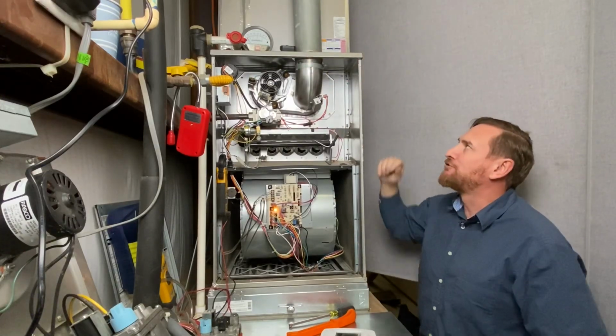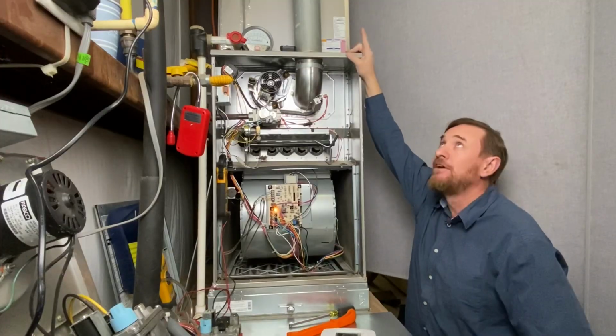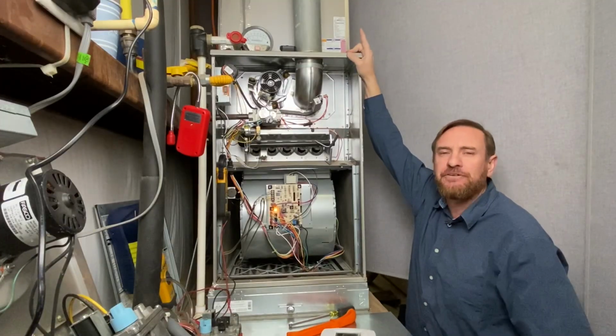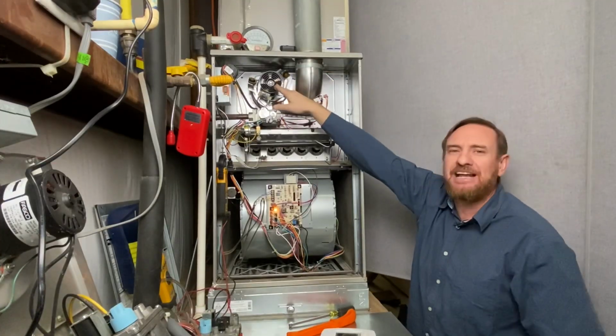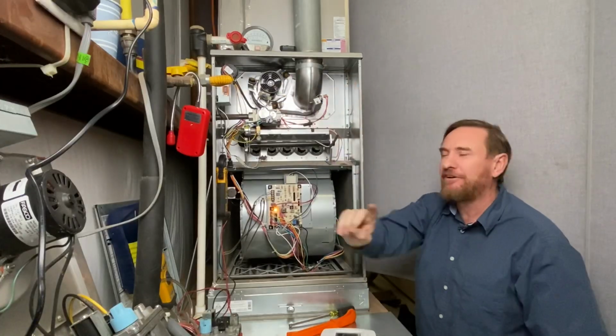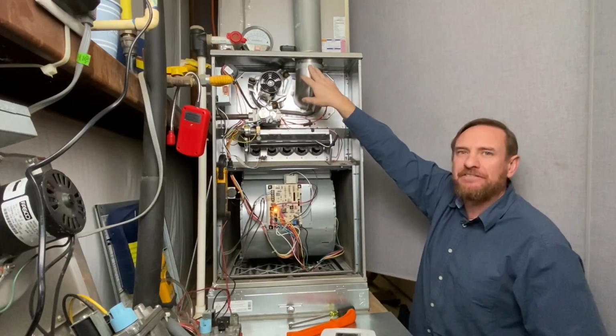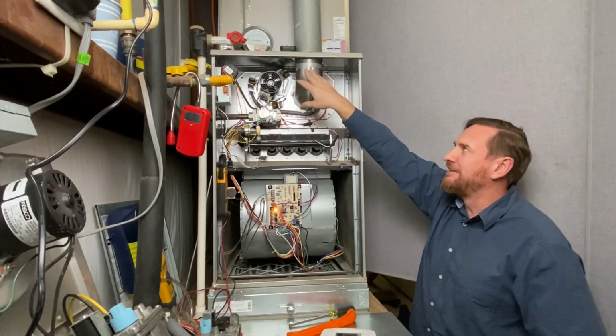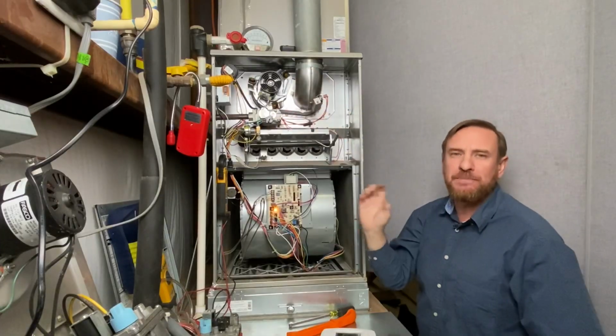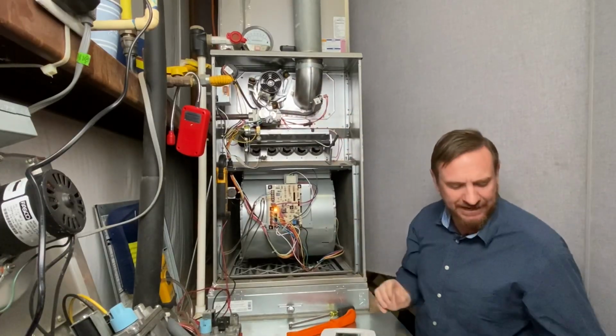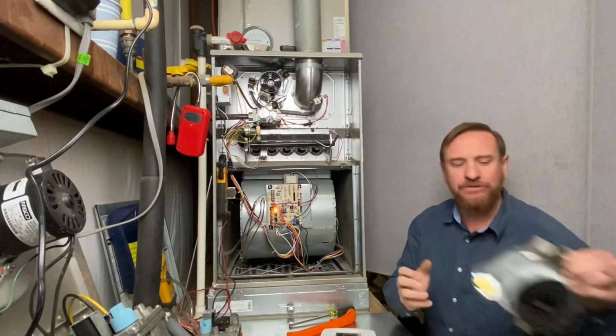A lot of people have tried to use different types of piping or different types of vents on the roof, and they think that as long as it's pushing it out, they don't have anything to worry about. And that's false. This is a natural draft. The only ones that are positive pressure, with a different type of heat exchanger, usually the ones with PVC, that's the ones that are forcing it out. Now we're going to talk about this inducer fan motor.